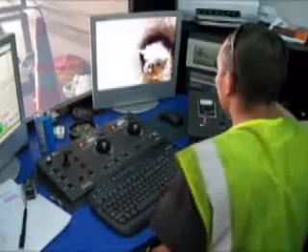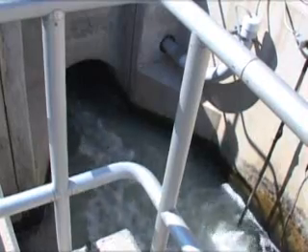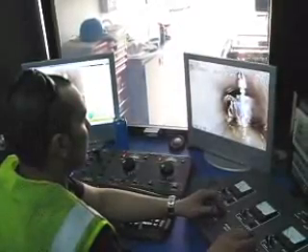This latter culprit increases the amount of water that finds its way to water reclamation facilities and can result in much higher than necessary treatment costs. To address this challenge, the Service Authority is lining the inside of pipes that connect houses to the sewer mains with a new material that is quickly becoming the industry standard. Heat is applied to cure the felt-like material and bond it to the pipe, which blocks water leaks and keeps flow to the treatment facility at manageable levels. So far, we're definitely satisfied — we've completed roughly 450 homes and are seeing a decrease in the amount of water infiltrating the system. The multi-stage, five-year project is in year two and is currently focused on lining pipes in the Flat Branch area of the county.